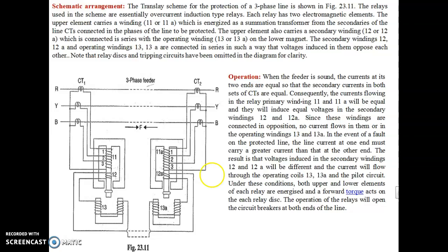See, how is the operation of this Translay relay? When the feeder is sound, the currents at the two ends are equal, so the secondary currents of the CTs on both sides are equal, so the currents flowing through the relay primary windings 11 and 11A will be equal, so equal voltages are induced in the secondary windings 12 and 12A. These windings are connected in opposition, so no current flows in the operating winding. Is it clear? See, the current is fed to the primary windings 11 and 11A.